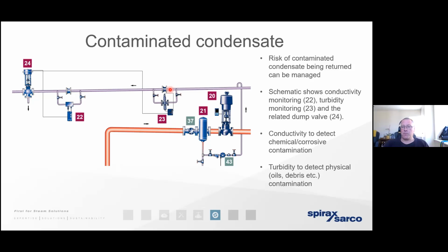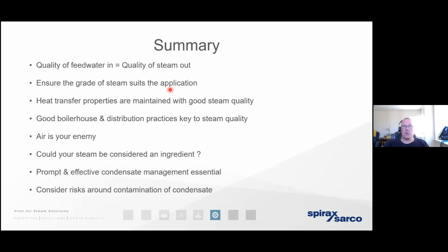the hot well. So there's a lot of information to go through there, and I appreciate you taking the time to bear with me this afternoon. But I'd just like to summarize very, very quickly that we're only ever going to get a good condition of steam if we're using a good condition of raw water, and if that raw water is being chemically conditioned appropriately. We also know that talking about a good condition of steam is going to mean different things to different people.